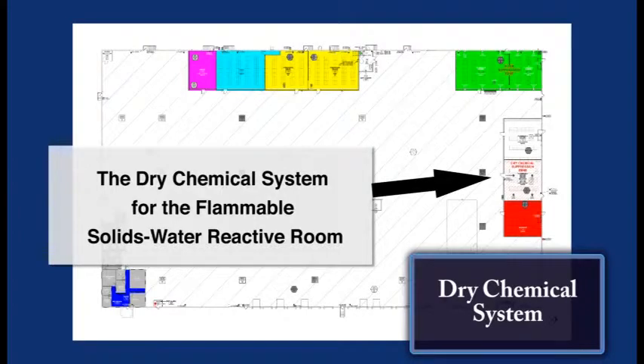A dry chemical suppression system provides coverage in the flammable solids water reactive storage room. The Kidde IND system is a dry chemical fire suppression system with two types of agents. The system utilizes stored pressure agent cylinders. Stored pressure cylinders remain free of contamination, reduce the packing of the agent, and provide a smooth flow throughout the discharge. The system can be activated electrically through the control panel. Cylinders are actuated from stored high-pressure nitrogen. Automatic and manual actuation is installed in this facility.